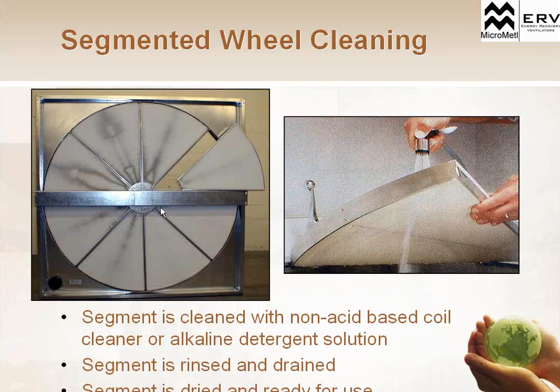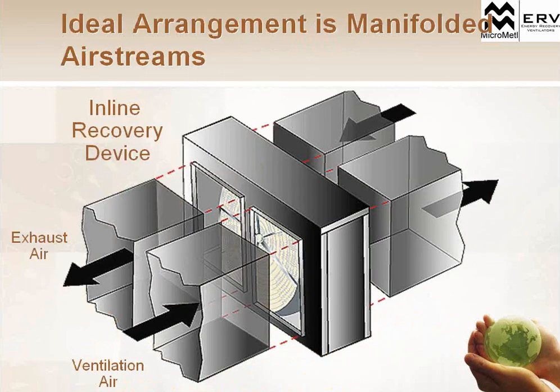As we talked about, the segmented wheel. These wheel pieces are not only segmented for installation, but also for cleaning. We're going to pre-filter the air, but basically we want to keep that wheel clean and make sure there's nothing clogging it, as you can see, those plastic polymer sheets are pretty close together. So we want to take those out at least once a year. You can bring them out and hose them off with a non-acidic cleaner or an alkaline detergent solution. Most of the wheel cabinets slide directly out of the ERV, so if you're lucky enough to get a hose on top of the roof, you can bring them out and just spray them down. It's very easy to clean.